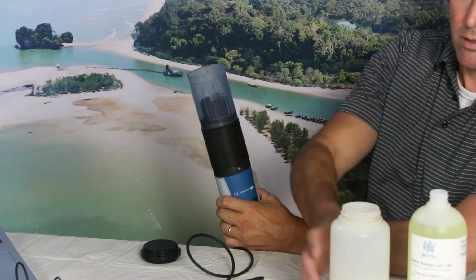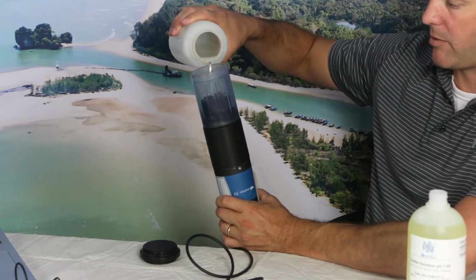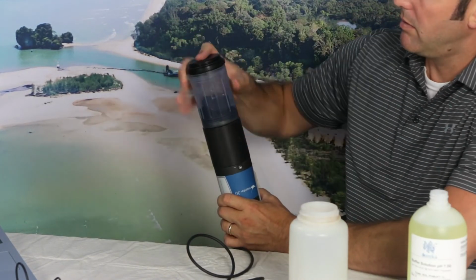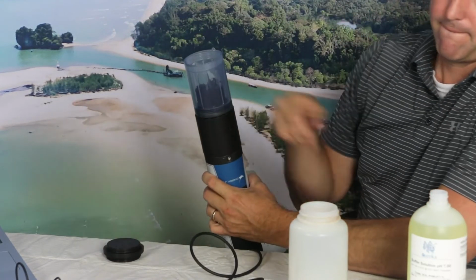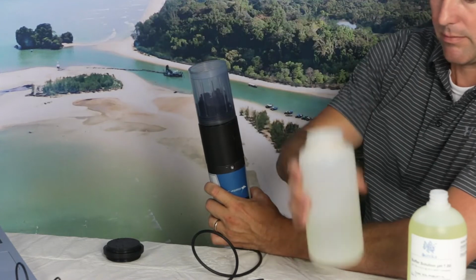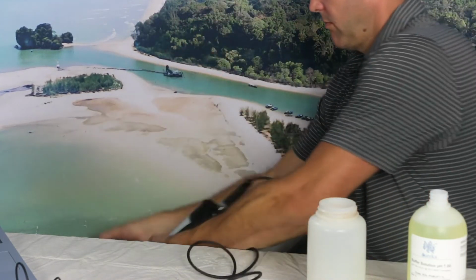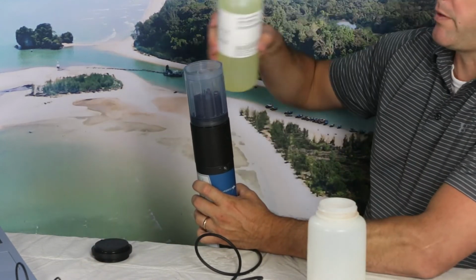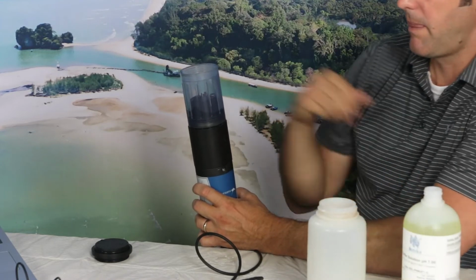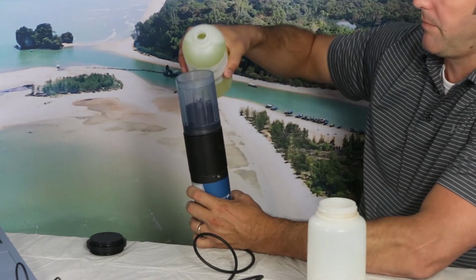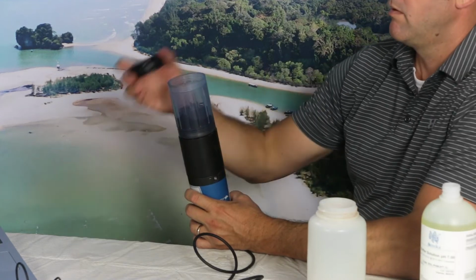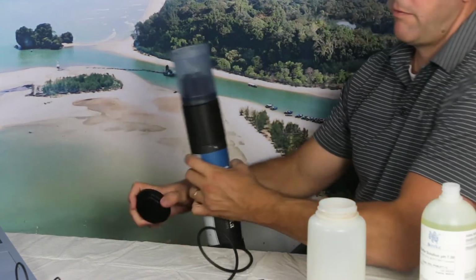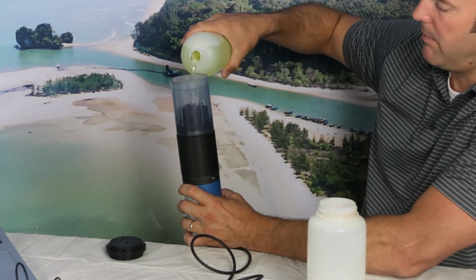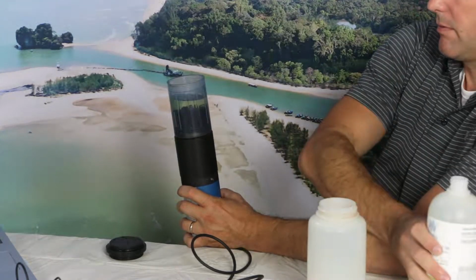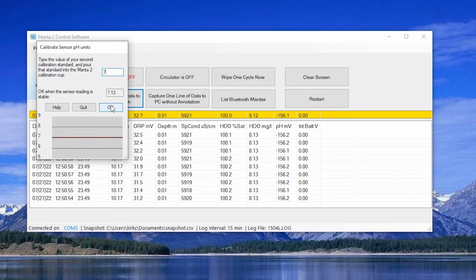To calibrate your second point, we're going to do our rinsing process once again with our DI or RO water. Second rinse with water. Then 2 rinses with our 7 buffer. Then finally, fill the cup up to where all of your sensors are submerged. Wait for the reading to stabilize, and then click OK.